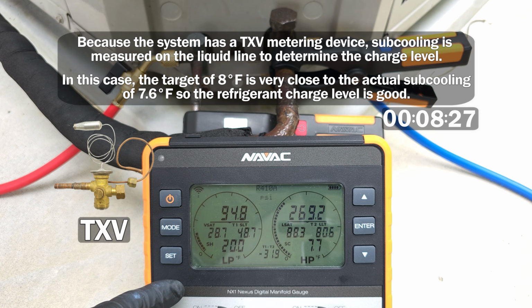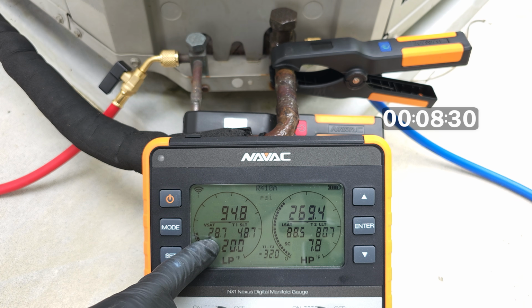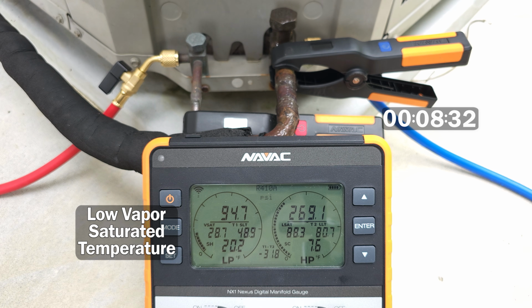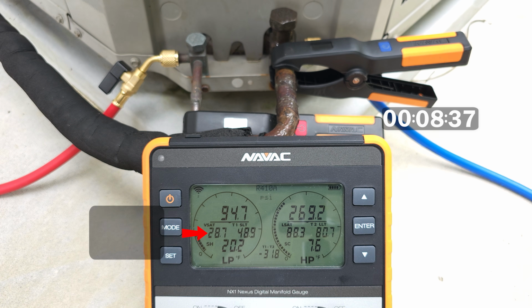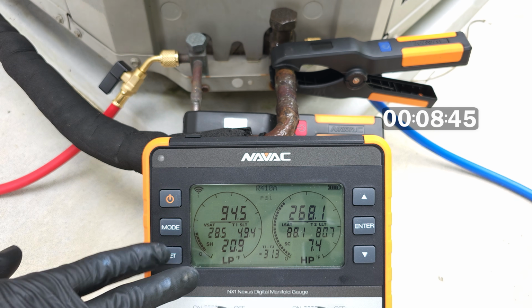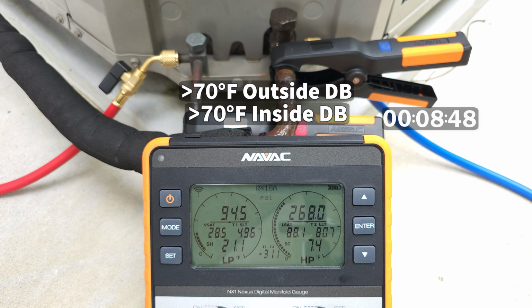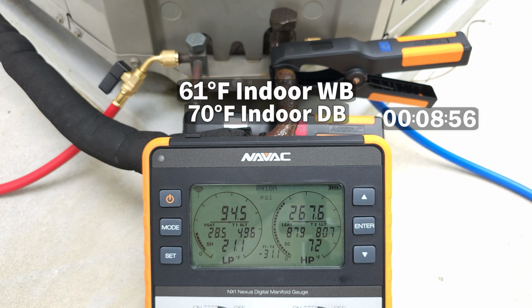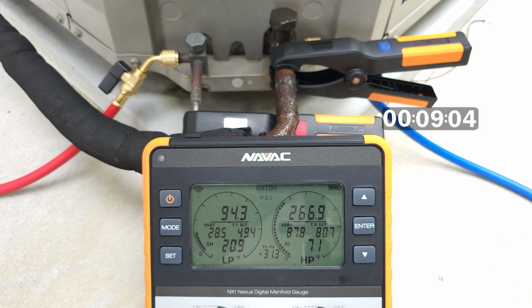Now, as far as the vapor line goes, we have a very low saturated temperature, which means that we have a low heat load at the indoor coil. So that means either we have low airflow or basically the temperature inside the building is very low. But before you check the refrigerant charge on a system, you want to make sure that it's at least 70 degrees inside and 70 degrees outside as a dry bulb temperature. So inside we have about 61 degrees as an indoor wet bulb temperature and 70 degrees as a dry bulb temperature. So we know that the indoor temperature is not the problem, it's the airflow.